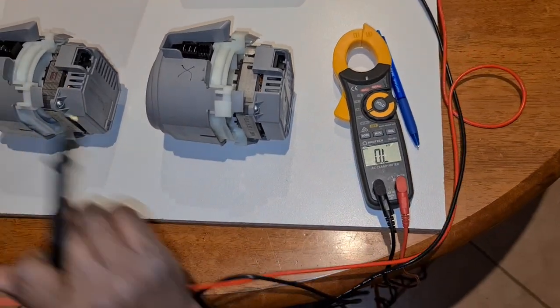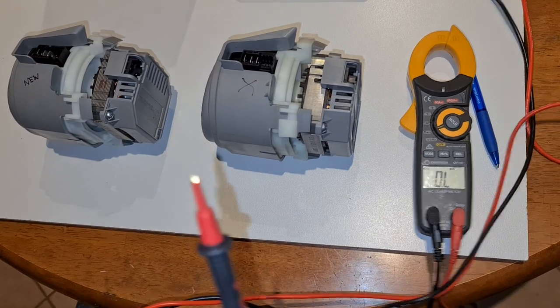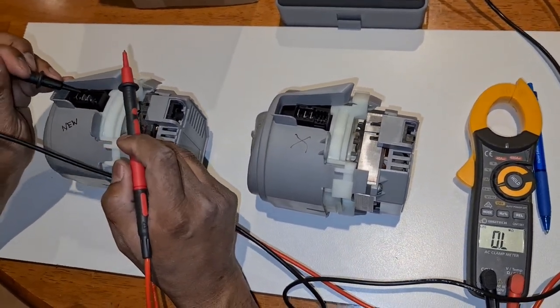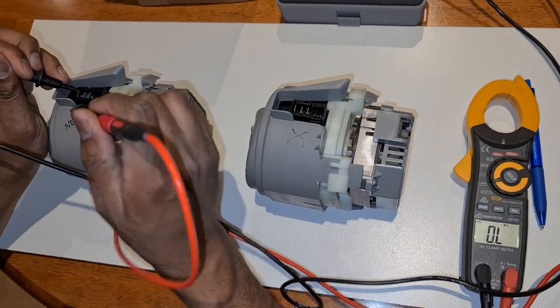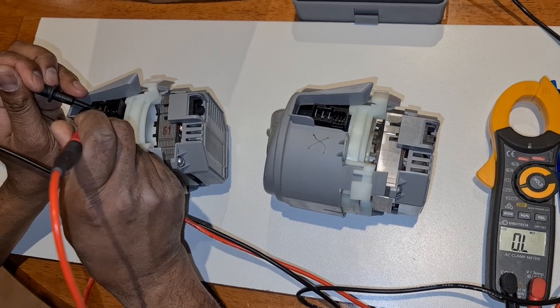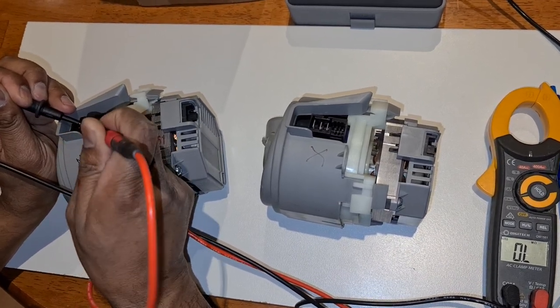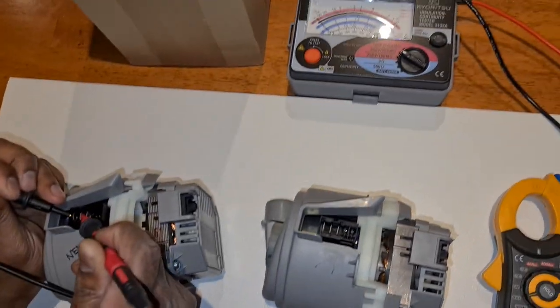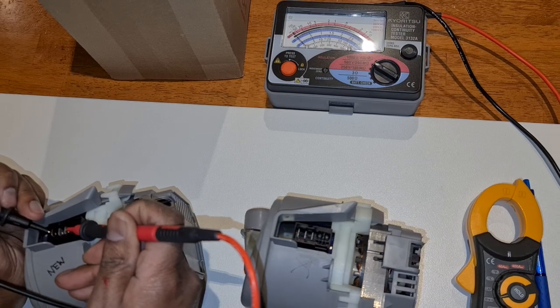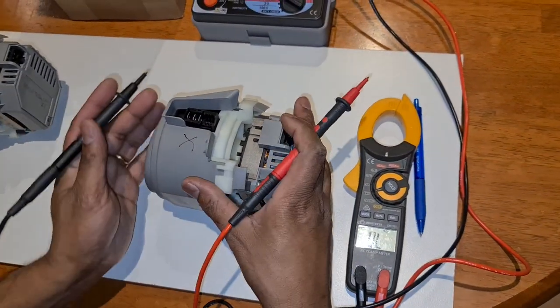So typically, when we do this type of test, we will do our first terminal over here, the earth terminal. That's the earth. Sorry, I need to get a good connection up there. And you have hardly any deflection on the instrument. So you do the second terminal as well, and same. So that's a good result. That's what we'd expect.